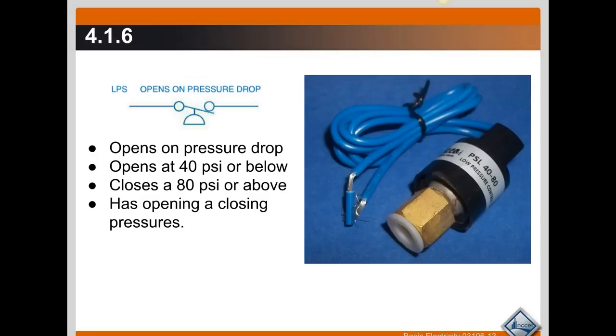A pressure switch is going to have opening and closing pressures. So when you look at these, you're going to be looking for these dashed numbers right here, and these are called the cut-in and cut-out pressures.